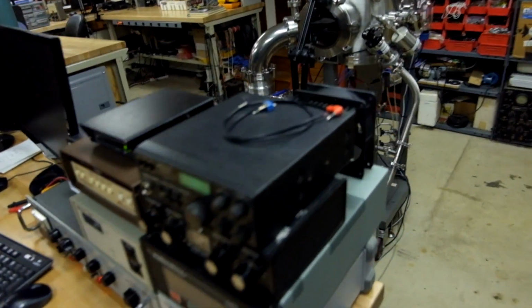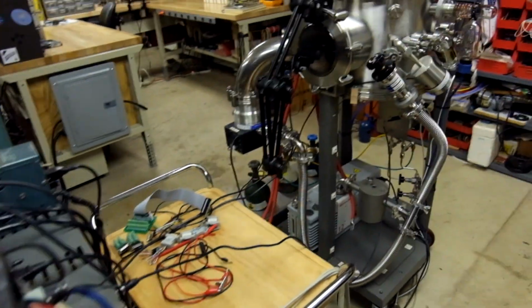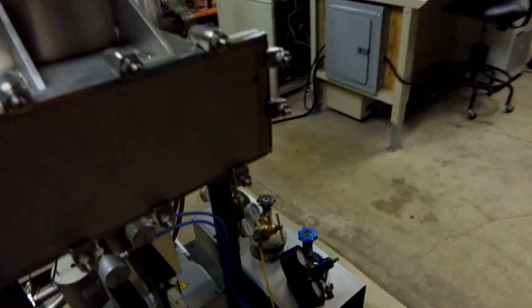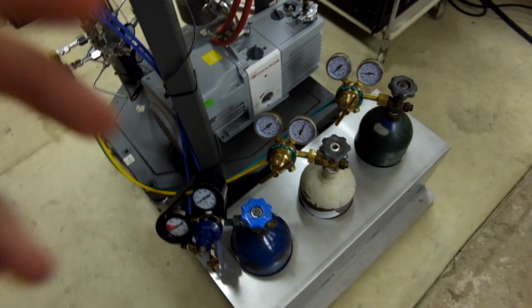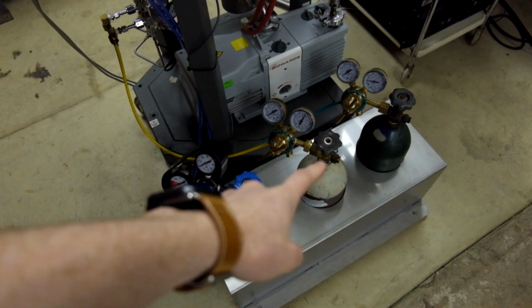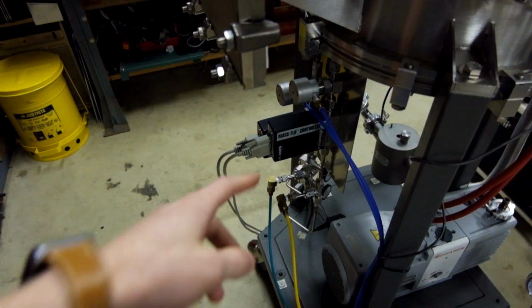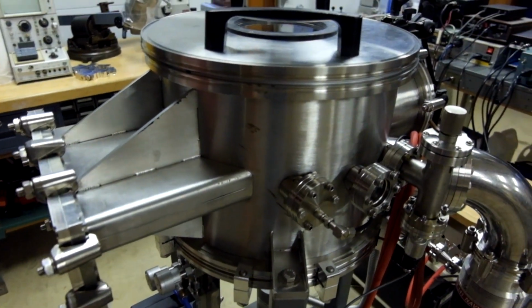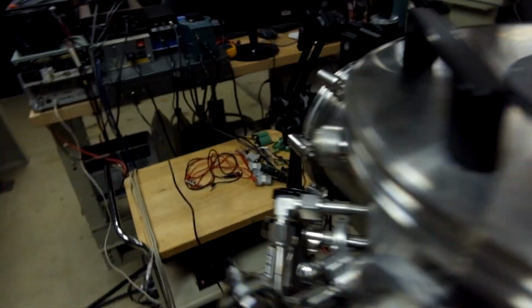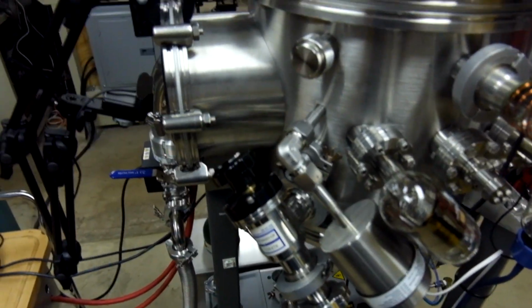I'm waiting for it to pump down, and I got bored, so I thought I'd show you how I prepare the samples. This is my high vacuum chamber, and right now it's set up for sputtering. So over here I have some gases. I can flow argon into the chamber via the mass flow controller very, very precisely. And, well, first I evacuate it with the turbo pump over there, and then once the blades in that slow down, I can allow argon back into it and make whatever partial pressure of argon I want.